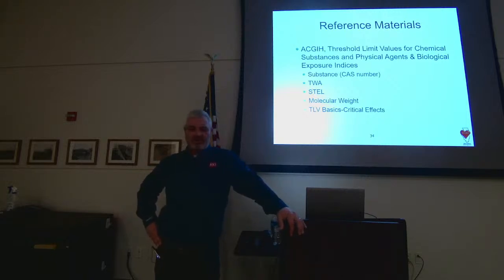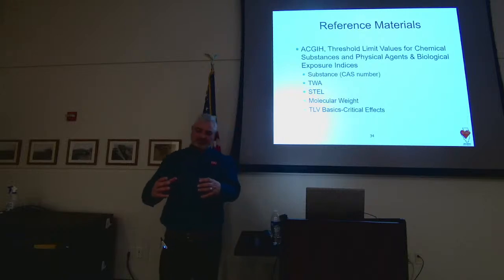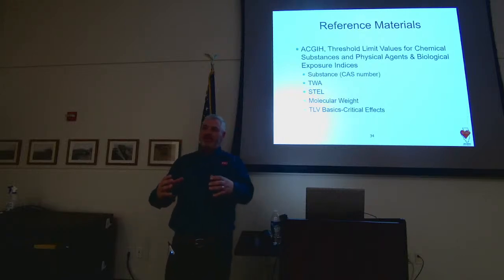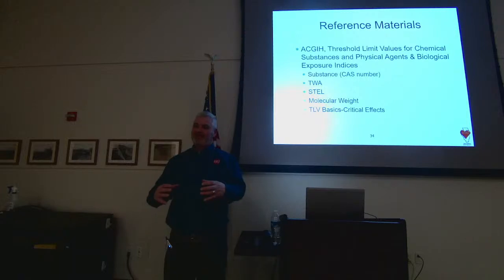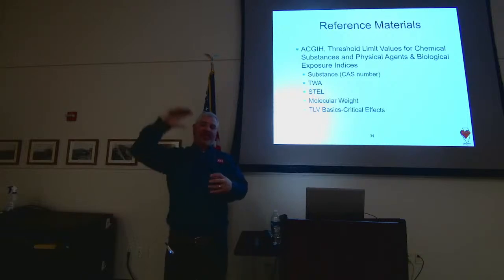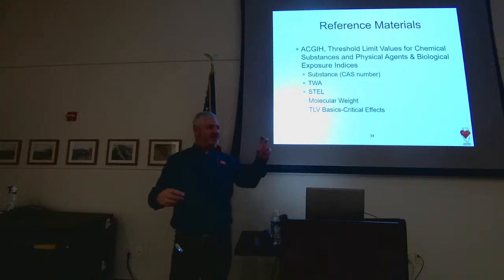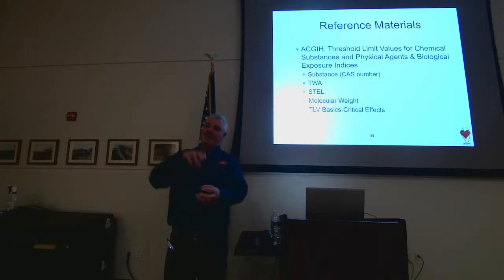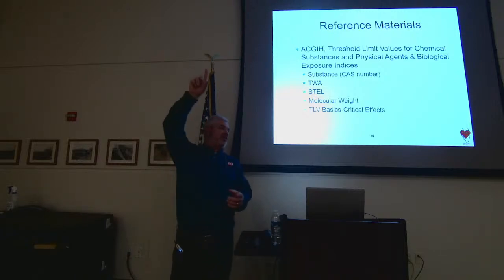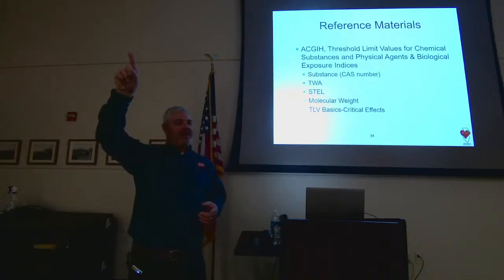Well, it turns out that in this particular instance, they had an H2S sensor. They'd calibrate it, but about once a week when they got influent dumped into it, the amount of H2S would not only go from 0 to 100, it would go way beyond 100. It would saturate that sensor, because that fuel cell is just a fluid reservoir. There were so many molecules of hydrogen sulfide in there that it would set every alarm off, shoot that value up to the roof, and ring every bell that he had.